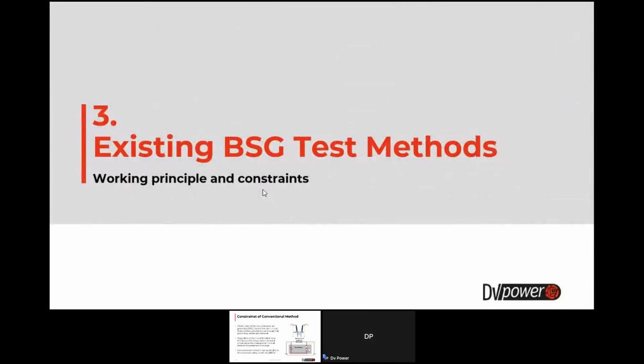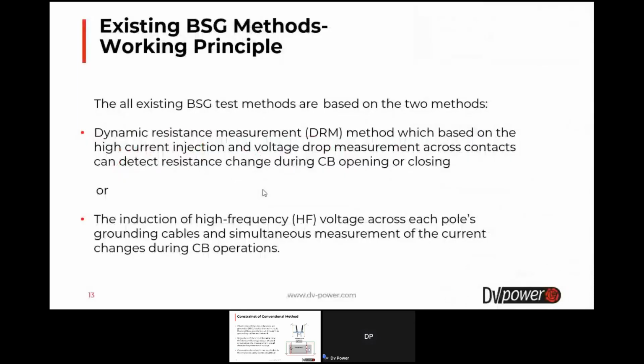On the market, there are already test methods for circuit breaker testing under both sides grounded conditions, but they also have some constraints that I'm going to try to explain. All existing BSG test methods are based on two main methods: the dynamic resistance measurement method, which is based on high current injection and voltage drop measurement across contacts and can detect resistance change during circuit breaker opening or closing. And the other one is the induction of high frequency voltage across each pole's grounding cables and simultaneous measurement of the current change during circuit breaker operations.